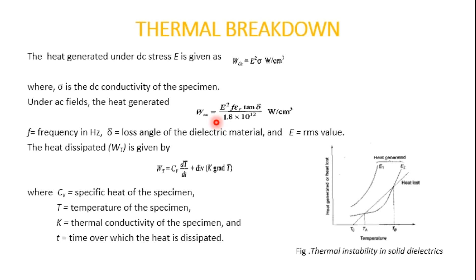For a given loss angle and applied stress, the heat generated is directly proportional to frequency — as seen in the W_AC formula. Hence thermal breakdown is more severe at high frequencies. This gives the thermal breakdown voltages of various materials under DC applications. The conclusion is: for AC, if there is a rise in frequency, the heat generated increases significantly, making it of great importance to choose the correct insulator size considering thermal breakdown.